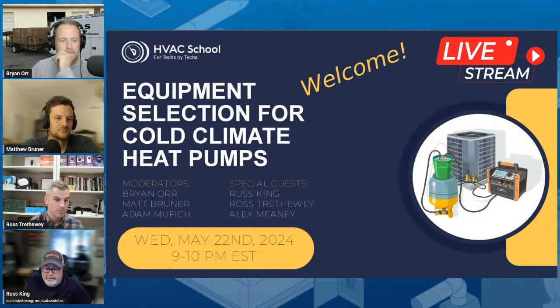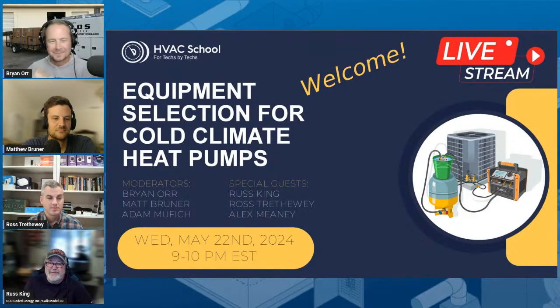Sure. I think the general problem that I'm seeing a lot of is contractors simply not doing load calculations and winging it. That's a huge problem. I mean, if you don't even know where the target is, how can you shoot at it, right? And I'm seeing a lot of that. They're using the size of the furnace that they're replacing as the basis for sizing the heat pump. And we all know that if there's AC in there, the furnace was sized for airflow. It wasn't sized to the heating load. And so they're off to a very bad start there. So I'm seeing a lot of that.